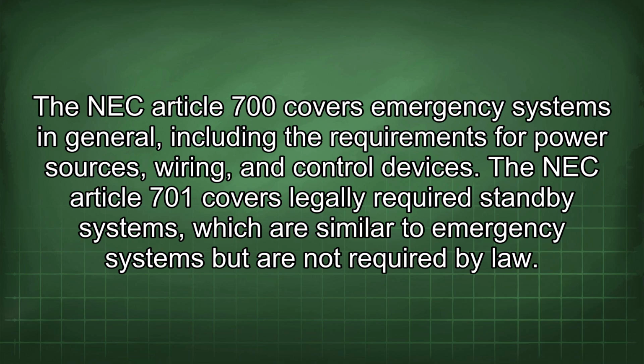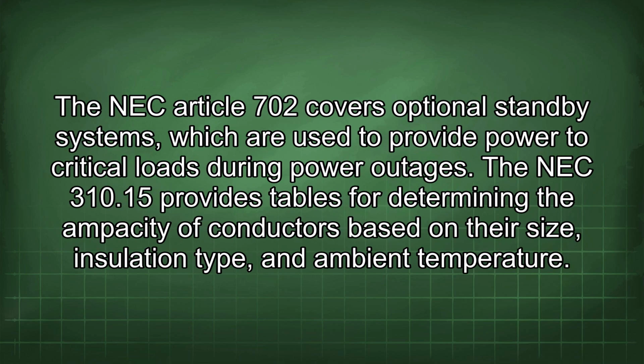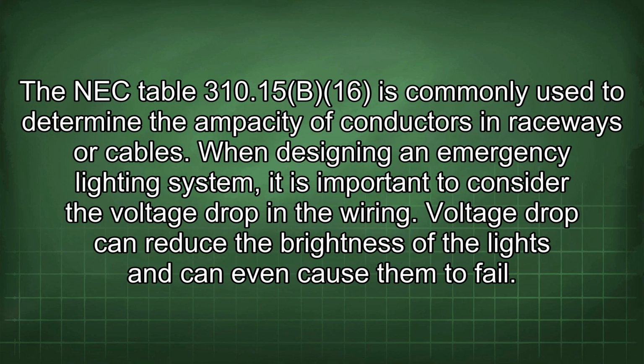The NEC Article 701 covers legally required standby systems, which are similar to emergency systems but are not required by law. The NEC Article 702 covers optional standby systems, which are used to provide power to critical loads during power outages. The NEC 310.15 provides tables for determining the ampacity of conductors based on their size, insulation type, and ambient temperature. The NEC Table 310.15(B)(16) is commonly used to determine the ampacity of conductors in raceways or cables.